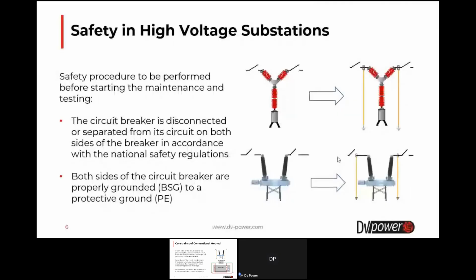Okay, so the safety procedure to be performed before starting the maintenance and testing is the following. The circuit breaker is disconnected or separated from its circuit on both sides in accordance with the national safety regulations. Then both sides of the circuit breaker are properly grounded to the protective ground, as can be seen in the figure on the right.